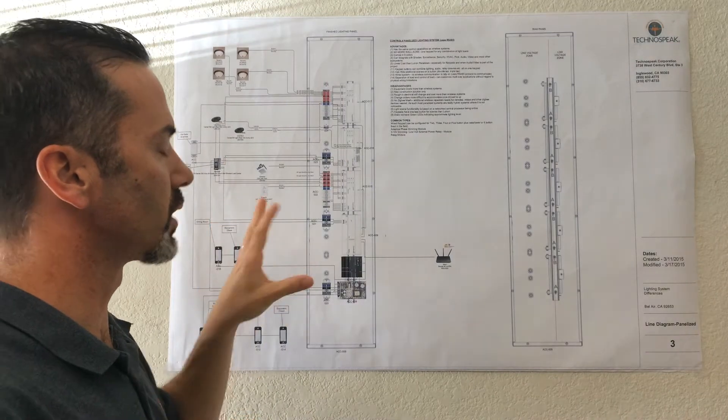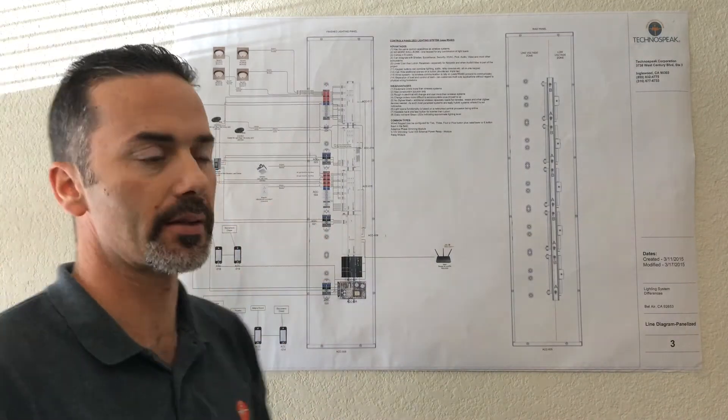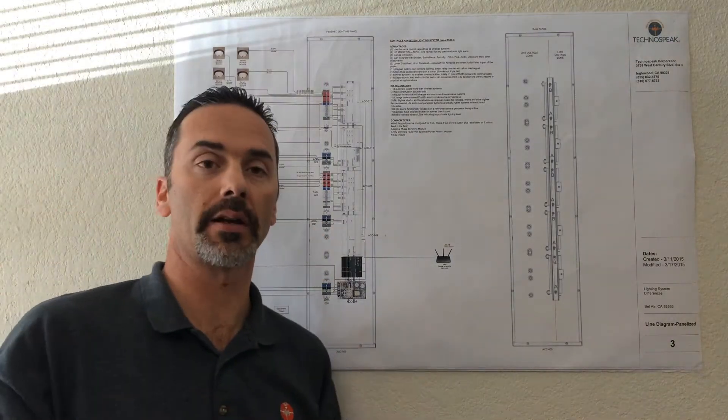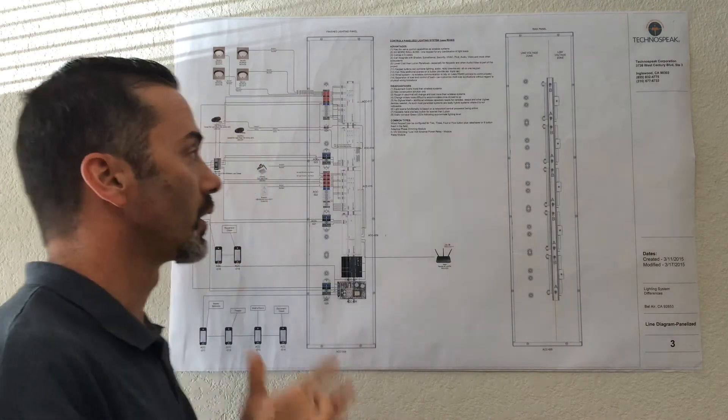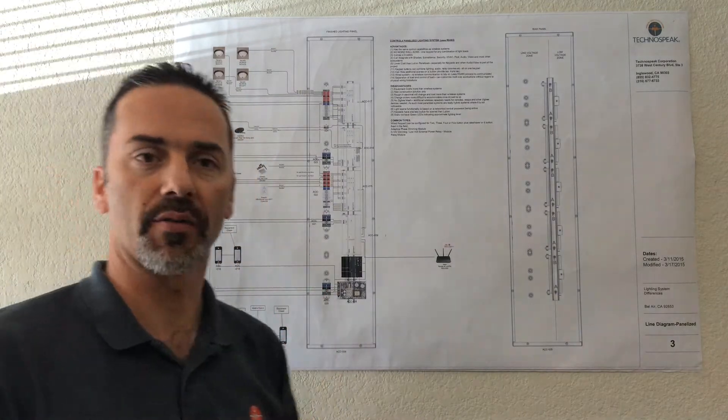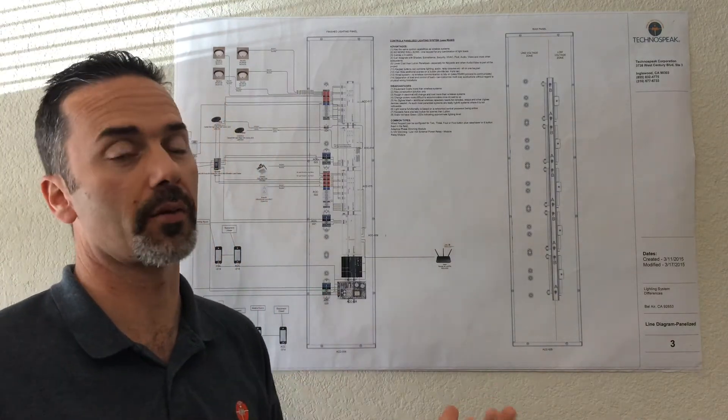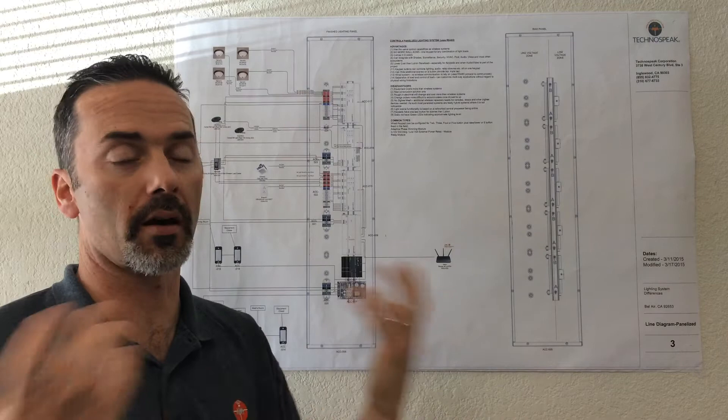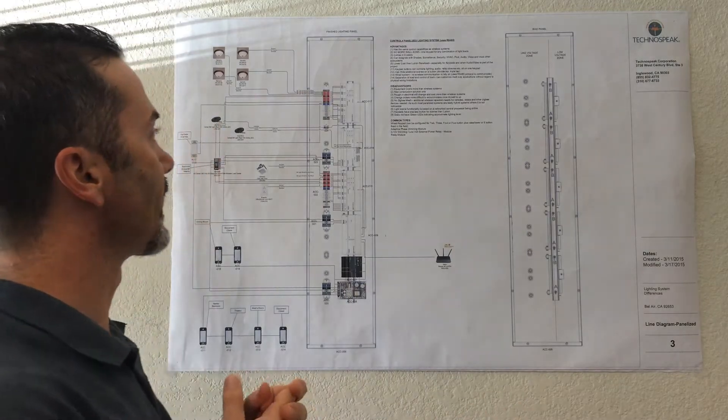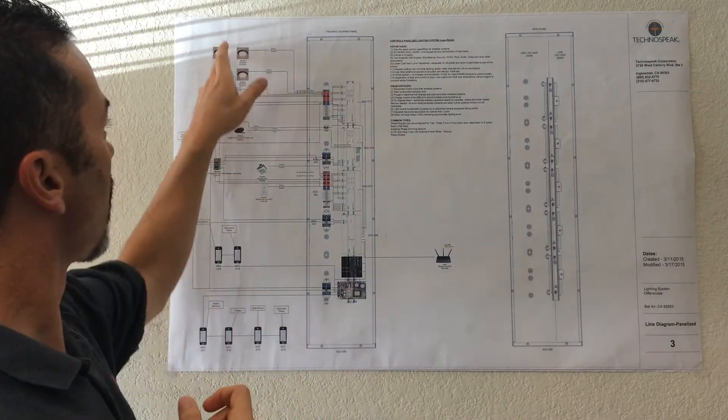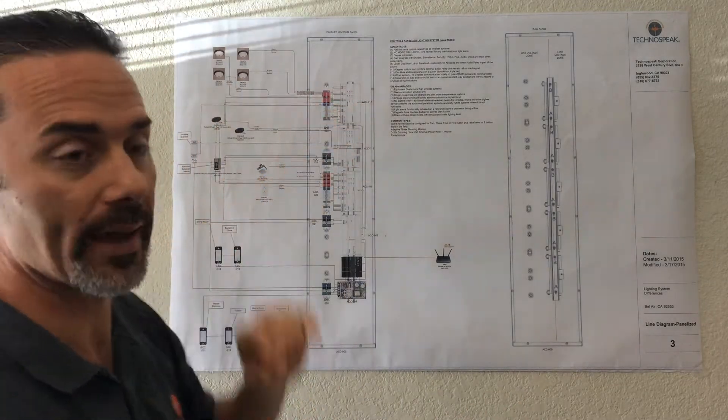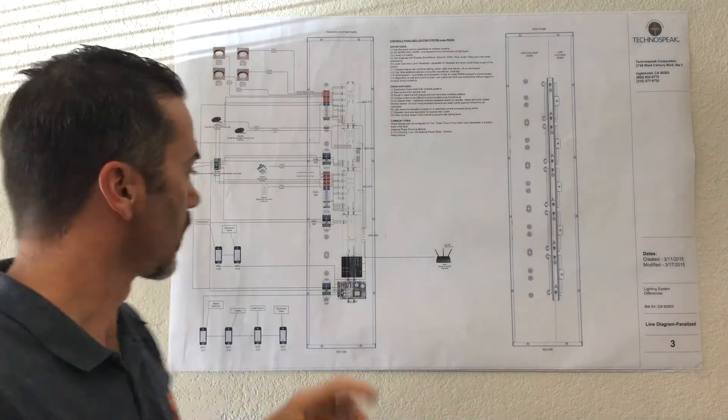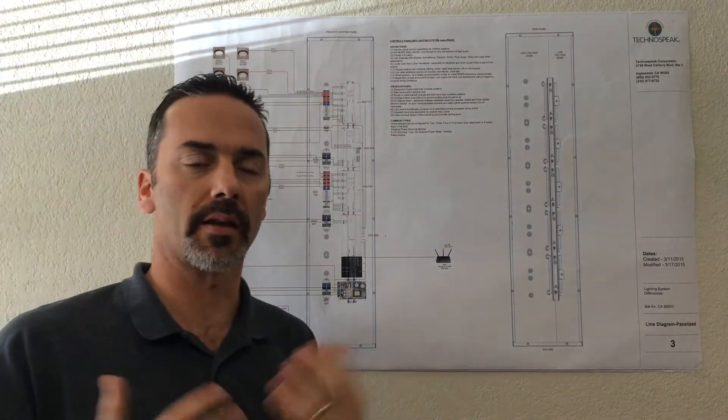The wired lighting system or panelized lighting system is definitely a new construction solution. You don't want to try and retrofit this into a home unless it's a significant remodel and basically all the drywall is stripped, and that's because all these lighting loads have to be run back to the panel versus to a light switch like in the wireless lighting system.